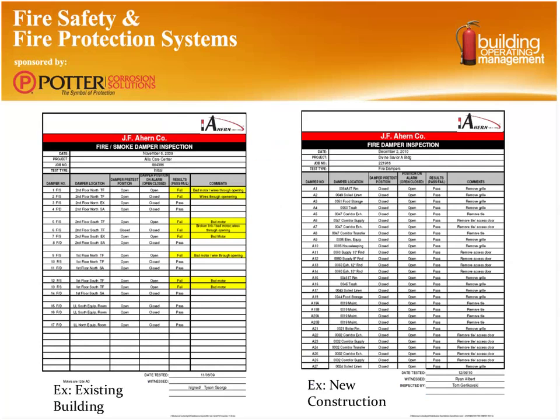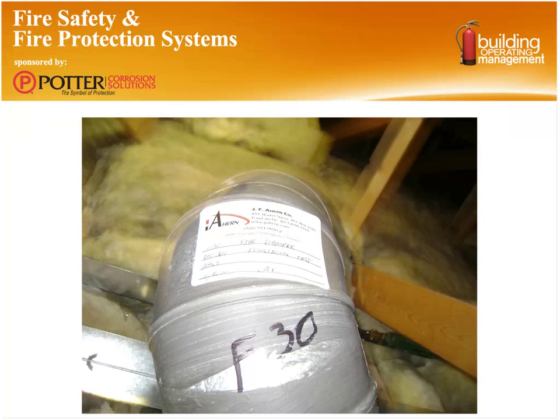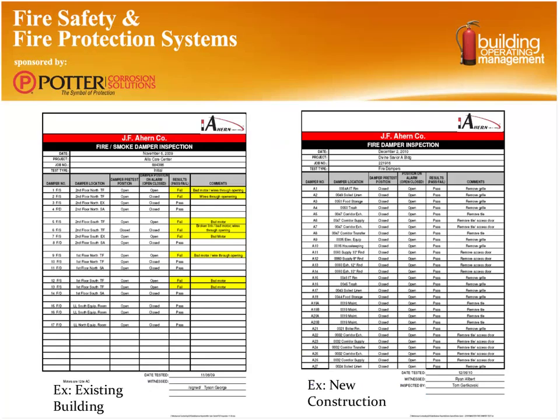So this is just a copy of some of the typical test reports that our company provides. They're a pretty common test report that most HVAC contractors do use. What these are doing is giving the technician a place to record his dampers, damper numbers, the fire dampers, the smoke dampers, the condition of them, and if there were any functional issues that need to be corrected. In addition to that, most companies will also tag those and number them. And the numbers on the tags and descriptions, again, reference back to that report. The idea being making it simple for the fire inspector and you as the building operator to understand, one, what needs to be fixed, and two, verification that it was actually tested.